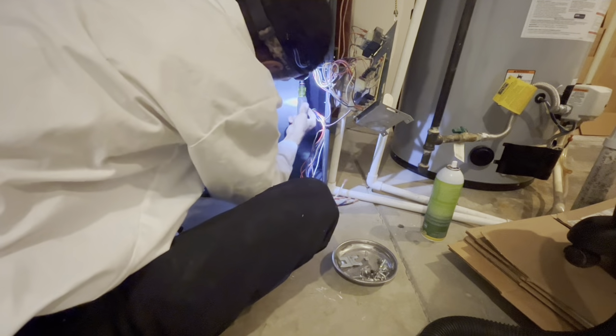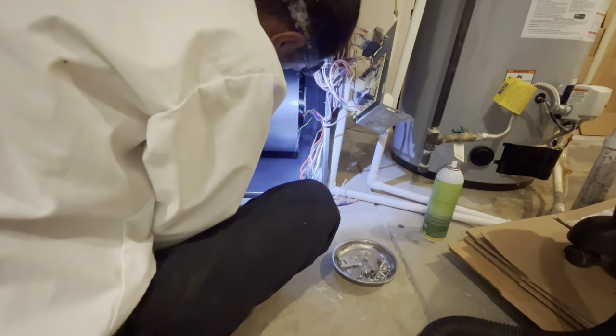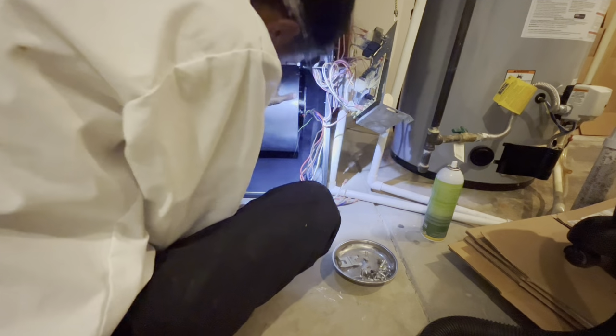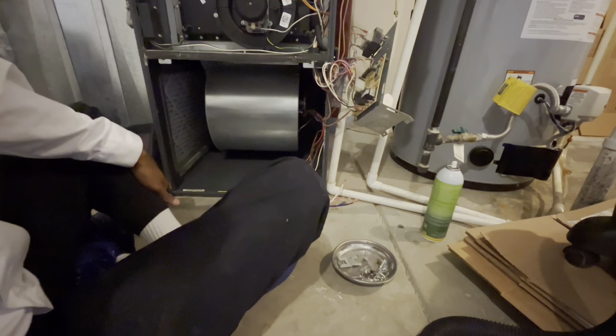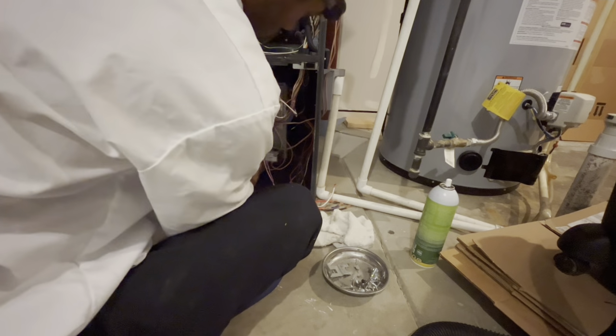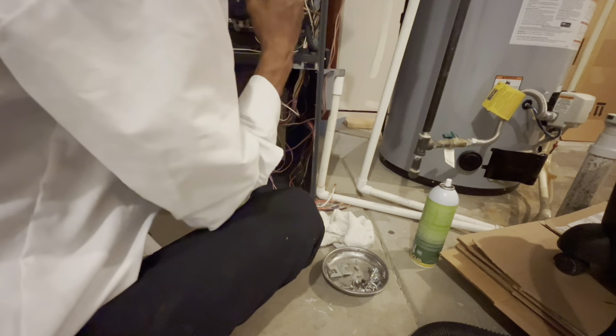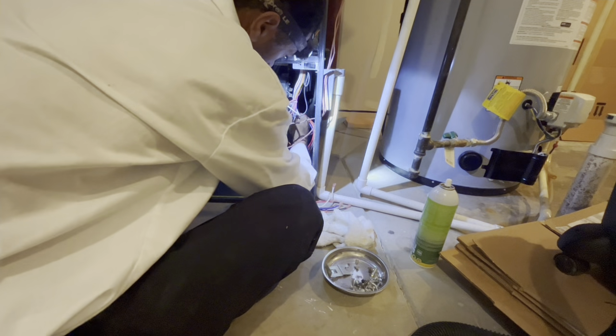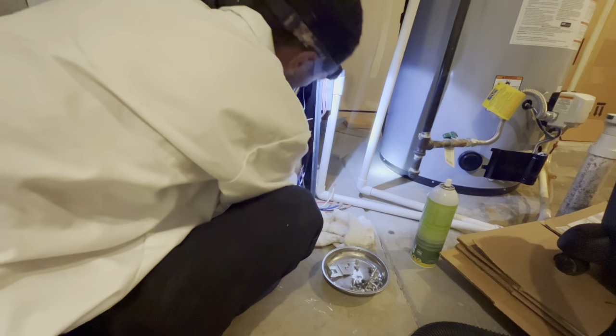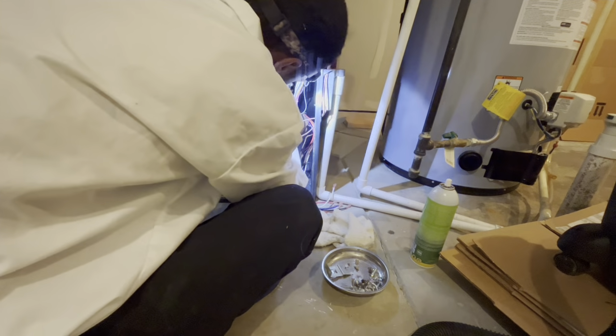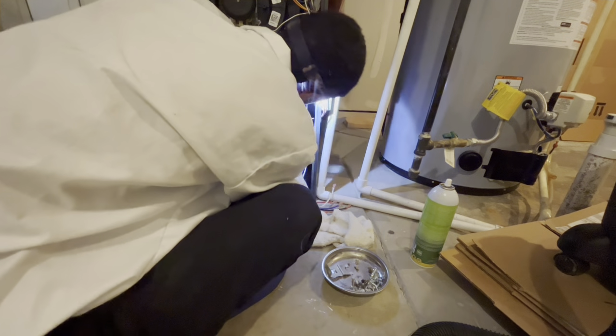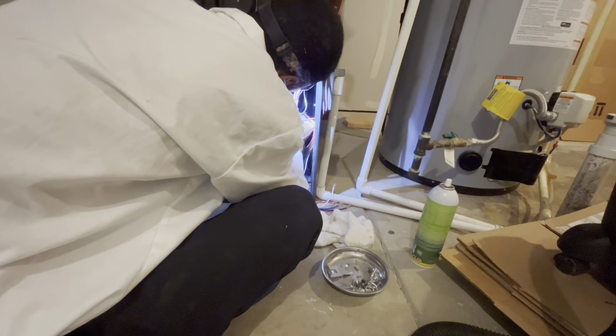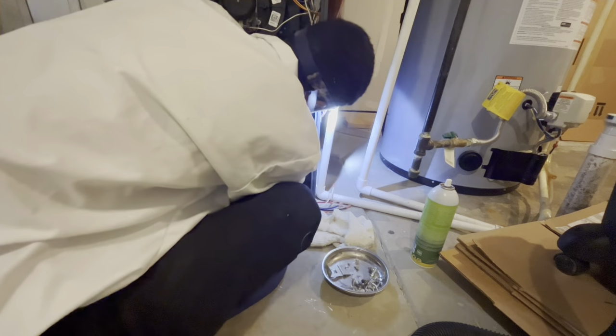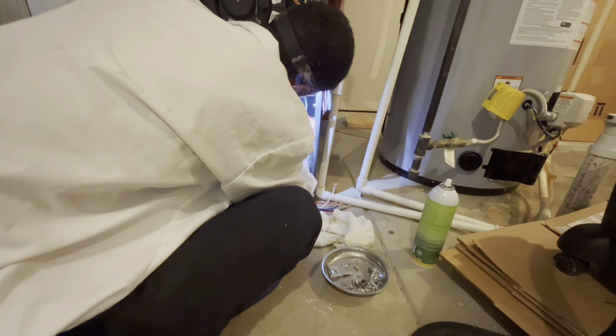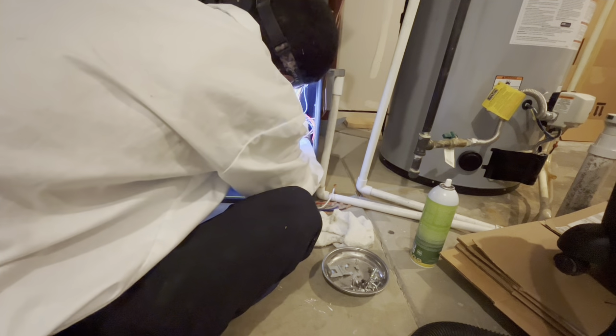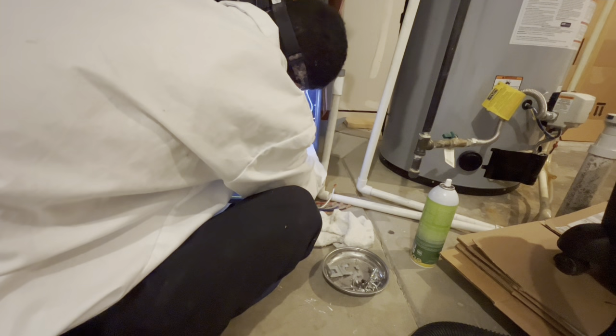So if you are putting in a new motor, please make sure that the motor will rotate in the right direction to move air throughout the house, because if it goes in the opposite direction, the system will not work. Especially on a dual shaft. You always need to actually test it out with 120 volts, just basically send power to it and actually make sure it moves air to the top of the furnace and not going to the bottom.